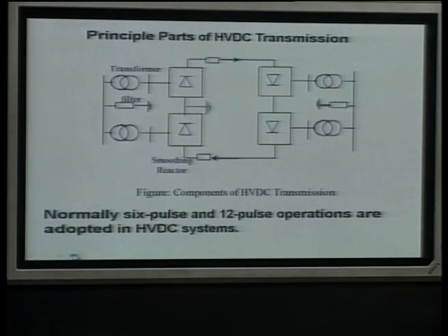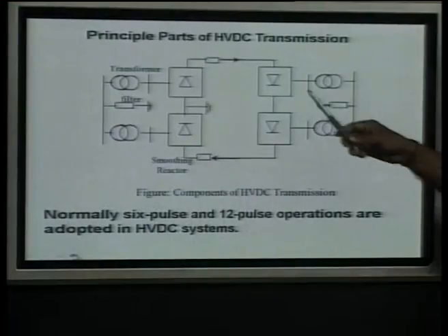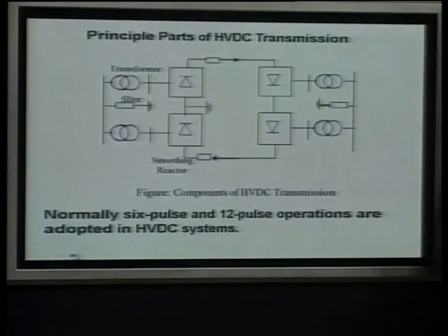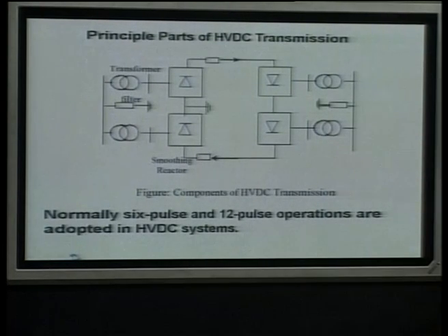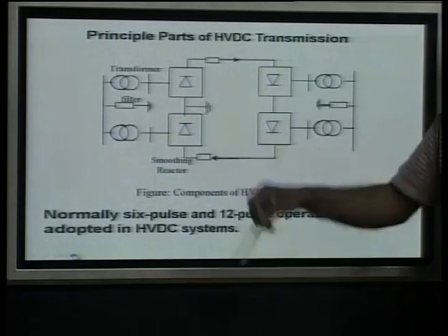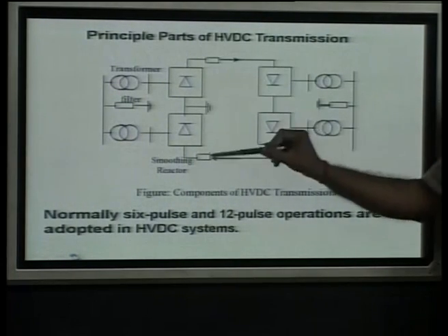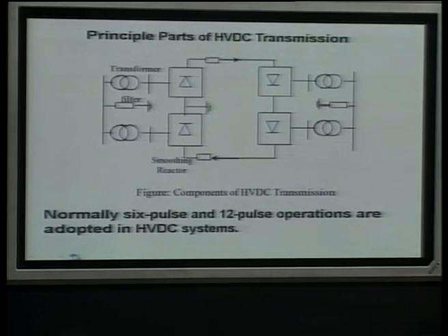and also a transformer at the inverter end. Apart from that, we have the filters, as you know, to filter out the harmonics, and these filters at the same time provide reactive power support at the fundamental frequency. They filter out the various harmonics, maybe the 5th and 7th or 11th and 13th, but at the same time they provide reactive power support to this station at the fundamental frequency, which can also be proved later on.